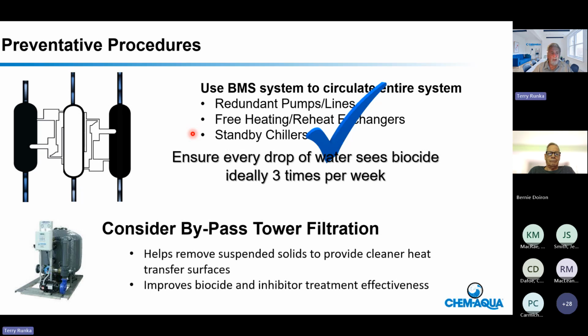Cooling towers are like great big old air washers, they suck all the dirt in the neighborhood in. That dirt is mostly suspended solids, while all the treatments and biocides are meant for dissolved solids. The biocides actually attach to those suspended solids and drop out instead of doing their job, so that dirt hurts you and hurts us. If you don't have a good cooling tower filtration system, there are all kinds available. A 10-inch filter housing probably won't help on a cooling tower, but a 30-inch bag filter or sand filter can. You don't need the high-end stuff, but any filtration you can add will help.